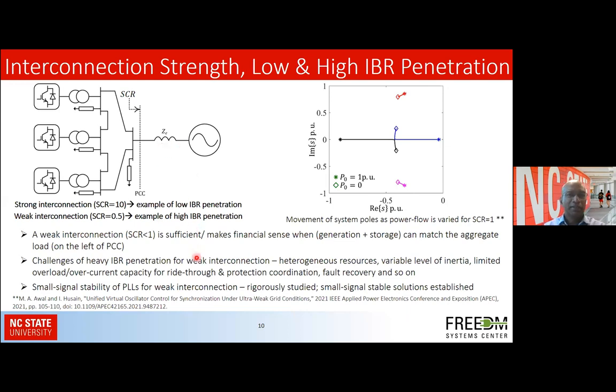But if the penetration is low, that means the short circuit ratio is high. This generation source should be able to take care of any fault that would occur here, and in that case, it may not be necessary to retain all of the grid forming converter capabilities for the IBR resources here.